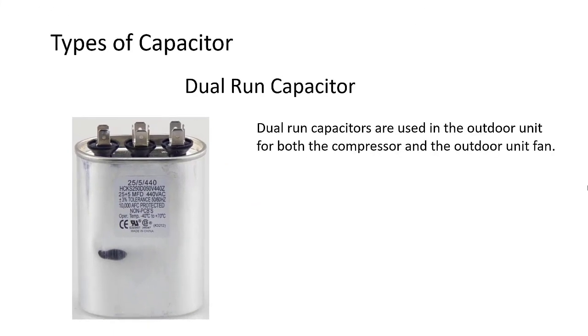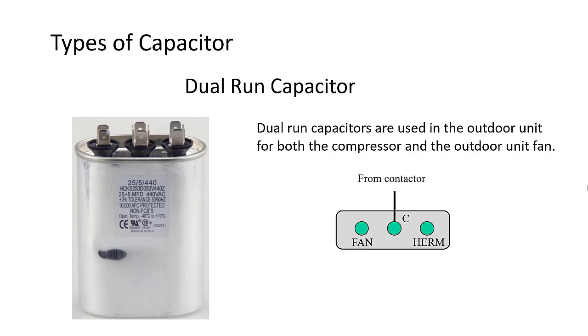Oftentimes in outdoor units with PSC motors, you will have a dual run capacitor. It is for both the compressor and the outdoor fan motor. They are wired up in a pretty straightforward fashion. HERM stands for compressor and fan for the fan motor. Don't get them confused as they require different farad settings.